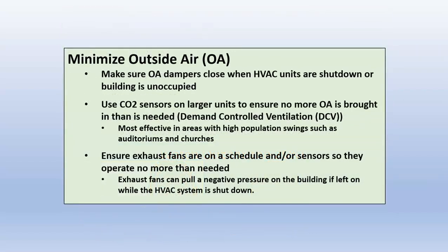You can use your BAS to minimize outside air. CO2 sensors, as we talked about, can measure the CO2, and that can be sent back to the outside air damper, and you can control the amount of outside air coming into the building based on occupancy or population. Now, this works really well in areas that have big swings in population, like auditoriums, churches, and schools.